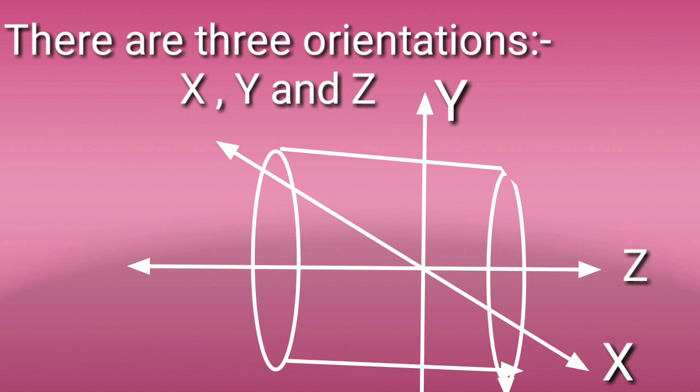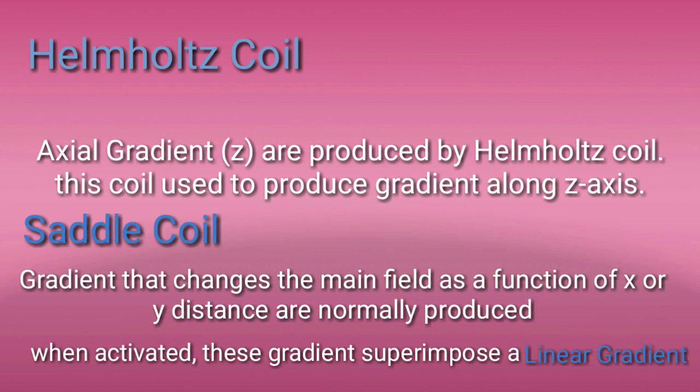The orientation of the gradient is along three directions. This shows the gradient working area. The first one is the Helmholtz coil, used along the Z axis. The saddle coil mainly changes the main magnetic field as a function of X and Y distance. A linear gradient is produced when the gradient is superimposed.